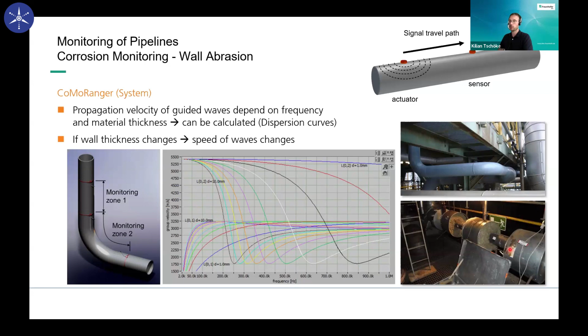If we have more sensors, we can get more information. But even this easy system, with only two sensors and one measurement box, can permanently monitor your pipelines for corrosion, especially in critical areas. One big advantage is you can put these sensors on positions where you have access, and monitor areas where you do not have access, for example elbows in a complicated structure, or again in power plants under isolation.